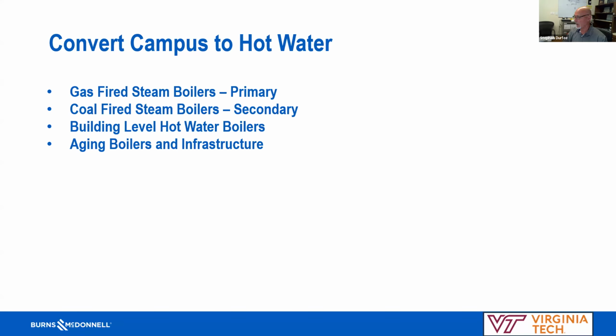So we partnered with Burns McDonnell to develop a strategic master plan where we'd look at moving away from some of these gas-fired steam boilers. We do have distributed boilers too, I'm sure MIT does as well. We have numerous buildings not on our steam distribution system, with either a steam boiler or even a high efficiency boiler within the building. But the long-term idea is to move away from this toward a typical low temperature hot water loop.